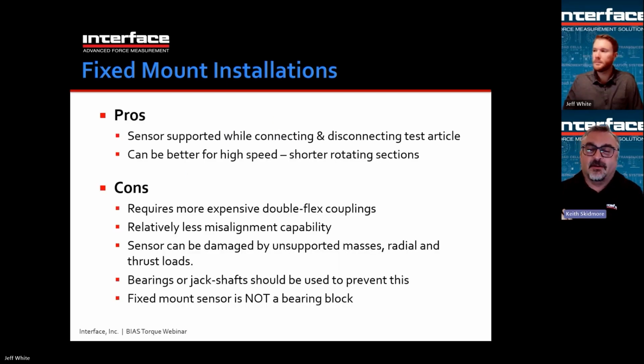So the pros of a fixed mount installation would be that the sensor is supported while connecting and disconnecting the test article. It can be better for higher speed because you have shorter unsupported rotating sections. Cons: it requires more expensive double flex couplings, and has relatively less misalignment capability because the couplings are short with just a little plate in between the flex points. The sensor can be damaged by unsupported masses and radial and thrust loads; it's not as well protected. The bearings or jack shafts should be used to prevent this.